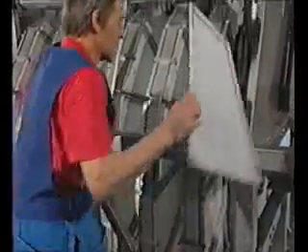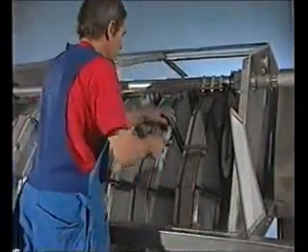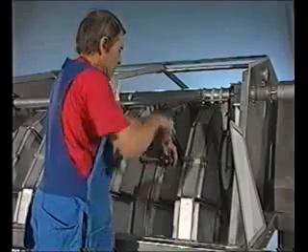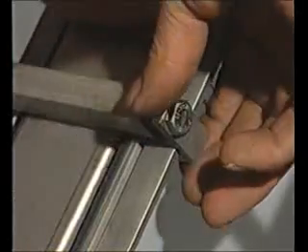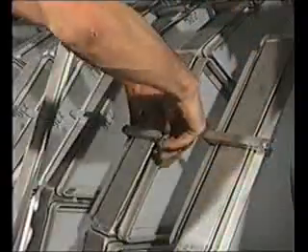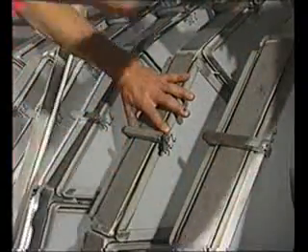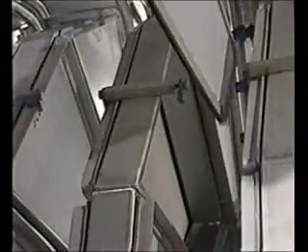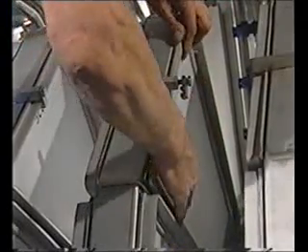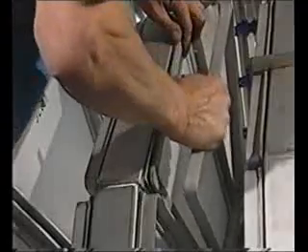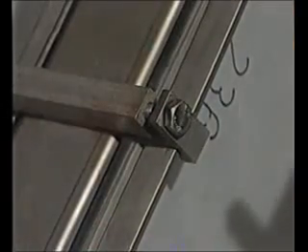The filter panel consists of a stretch filter cloth mounted on a stainless steel frame with an integrated rubber gasket. When the filter cloth is worn, the entire filter panel is replaced. The old filter panel can be used for recycling purposes. With the help of guide pins, the filter panel and locking frame are correctly put into position. The filter panel is held in position using a locking frame which is secured by a clasp and bolt.